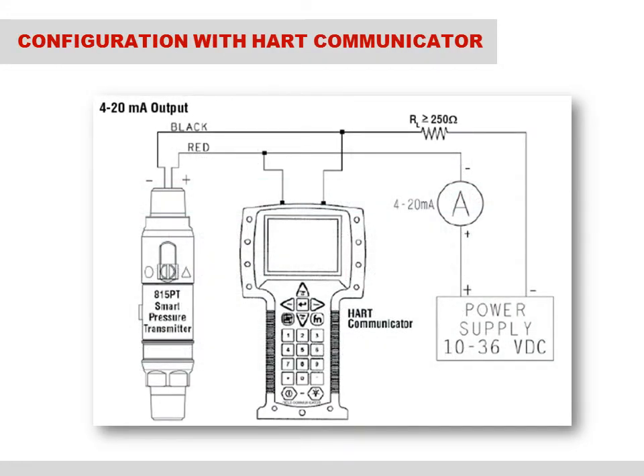On a previous slide, I discussed the different ways to configure, diagnose, and reconfigure an 815 PT smart pressure transmitter. Let's take a closer look at how to connect the HART handheld communicator, or HHC, to the 815 PT to configure the unit for a 4 to 20 milliamp output. Begin by connecting the HHC's lead set to the red and black flying leads on the 815. Connect the HHC's red lead to the 815's red wire and the HHC's black lead to the 815's black wire. So it's pretty straightforward, red to red and black to black.